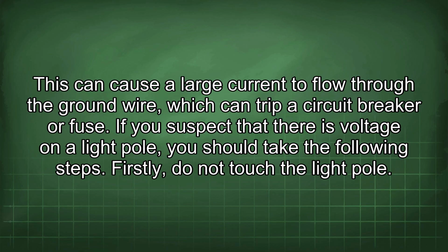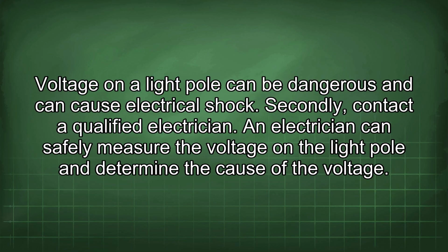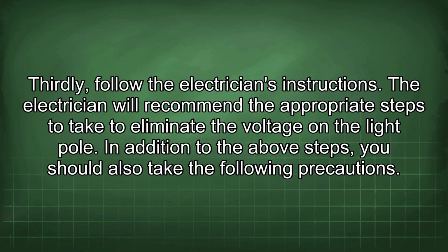If you suspect that there is voltage on a light pole, you should take the following steps. Firstly, do not touch the light pole. Voltage on a light pole can be dangerous and can cause electrical shock. Secondly, contact a qualified electrician. An electrician can safely measure the voltage on the light pole and determine the cause of the voltage. Thirdly, follow the electrician's instructions. The electrician will recommend the appropriate steps to take to eliminate the voltage on the light pole.